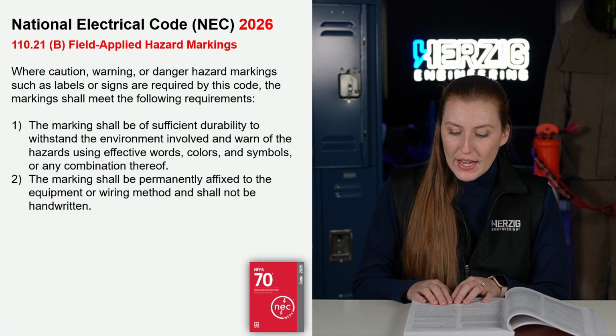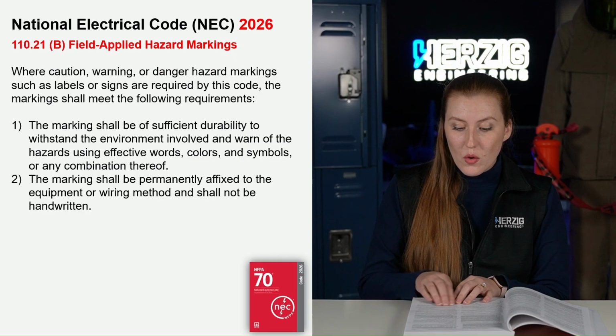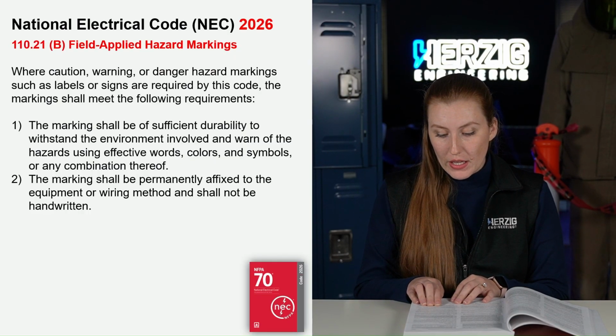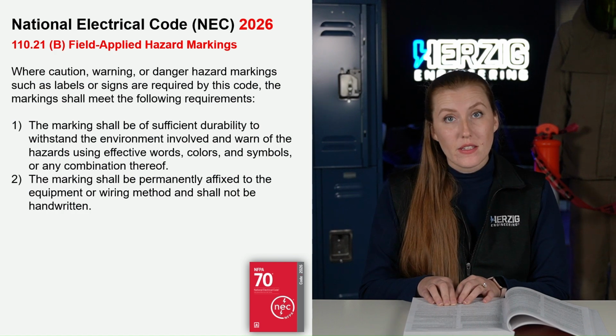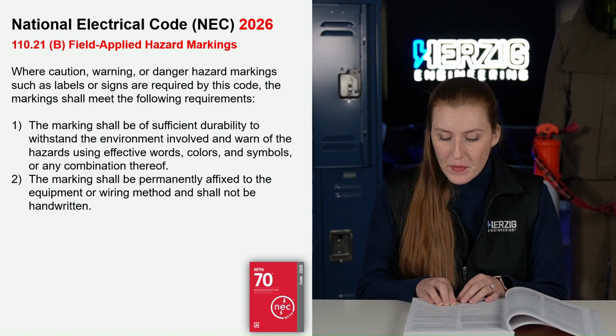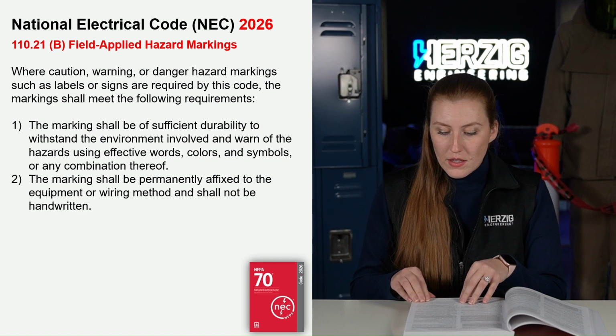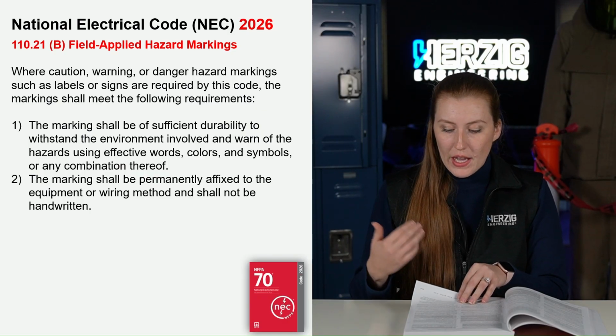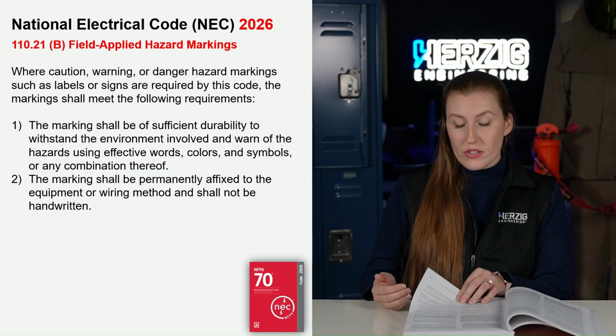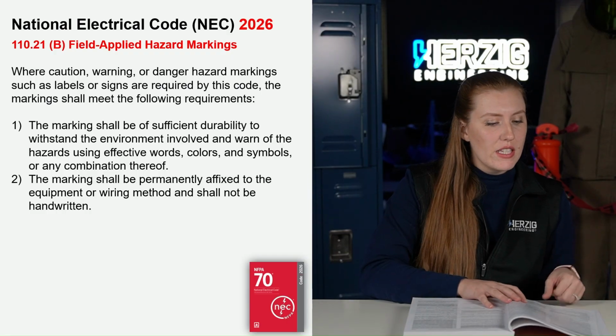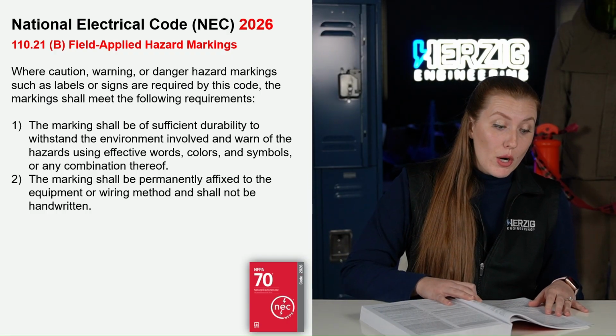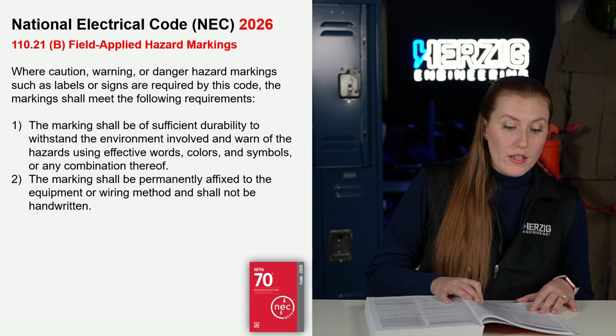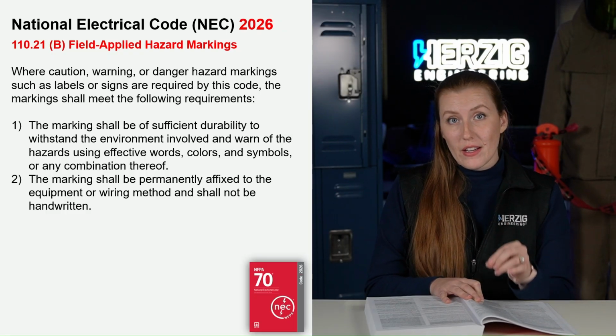Well, for the field applied hazard markings, it says where caution, warning, or danger hazard markings, such as labels or signs, are required by this code, 110.16, the marking shall meet the following requirements: be of sufficient durability and using the effective words, colors, and symbols per the ANSI Z535 standard, and the marking shall be permanently fixed to the equipment or wiring method and shall not be handwritten.